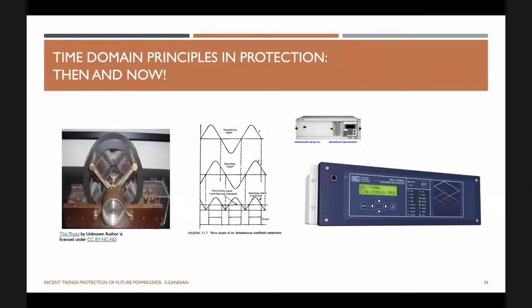At least I've had hands-on experience with that relay, and we used to have tripping in 500 kV systems within 2 to 3 milliseconds. It was a static output relay - we used to detect faults very fast. At the same time, we had made it a little bit slower on certain faults so that it doesn't misoperate. So there was a point beyond which you couldn't do much in that protection.